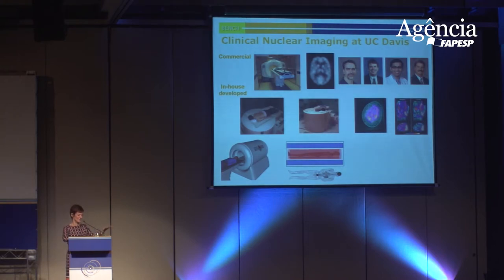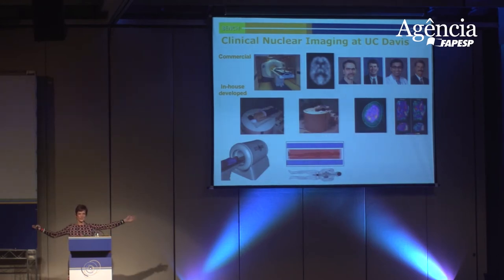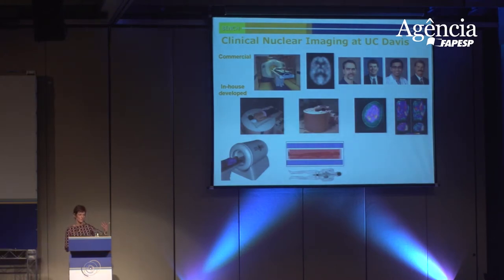The most recent development — our colleagues have a fundable score with the NIH to build a whole body PET scanner. In the clinic now, the patient moves through a field of view. When they finish this scanner, it's two meters long — the patient will go in, be scanned, and come out. They're also building detectors with high resolution and sensitivity so you can inject one-fiftieth of the radioactivity. This is great for our field: it will allow us to do normal volunteers, imaging of microbiota, and imaging children as well.